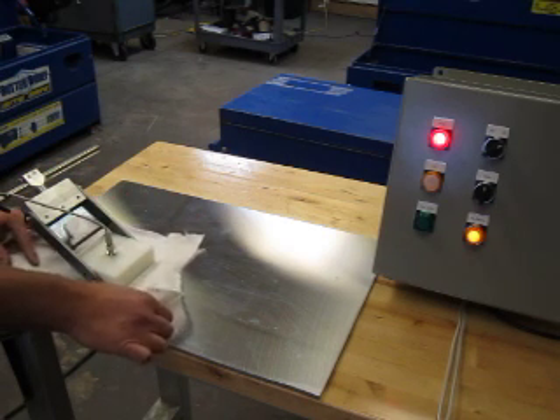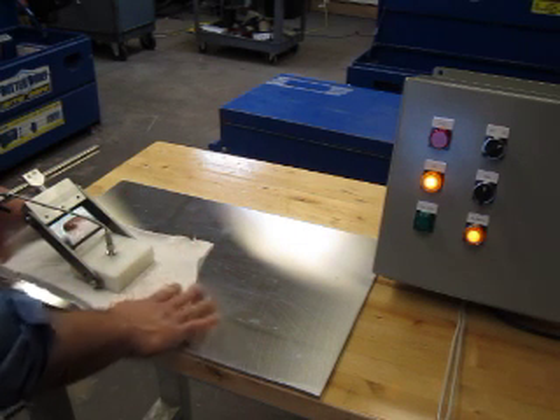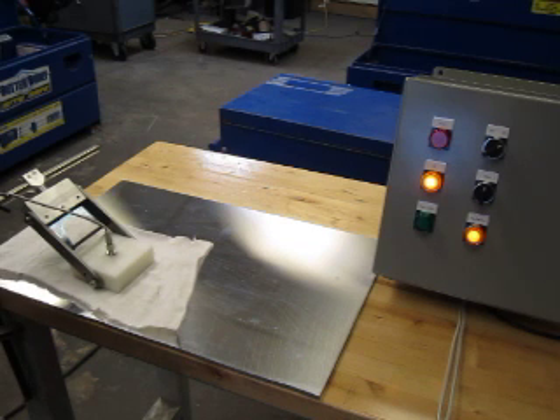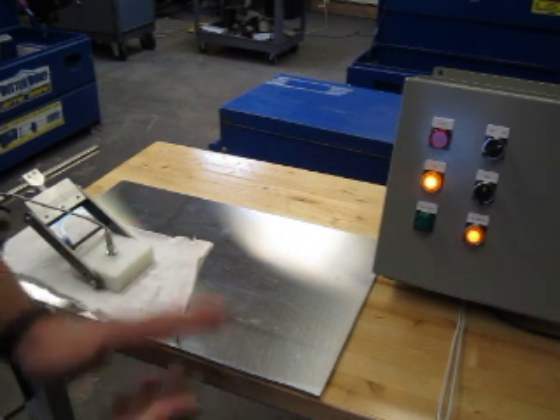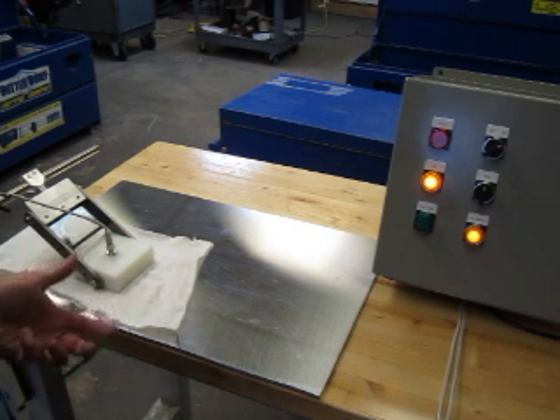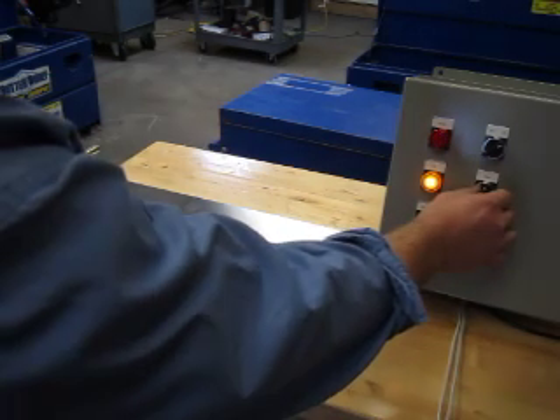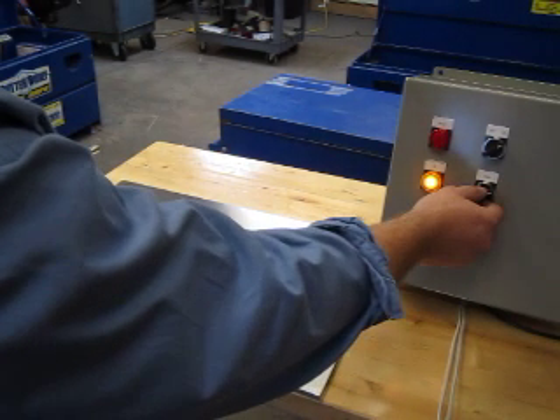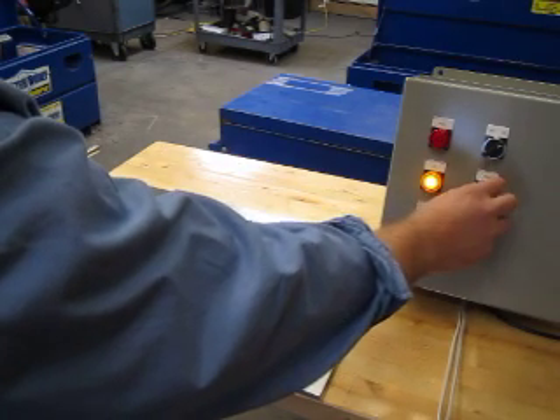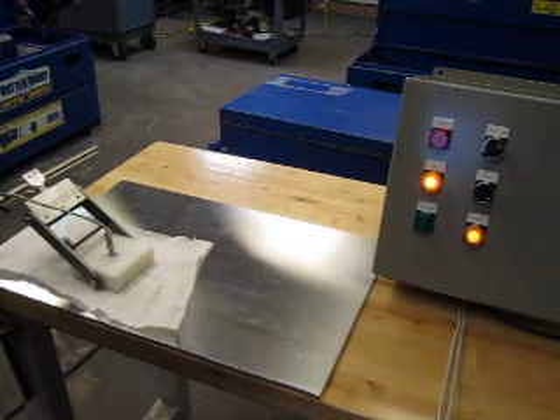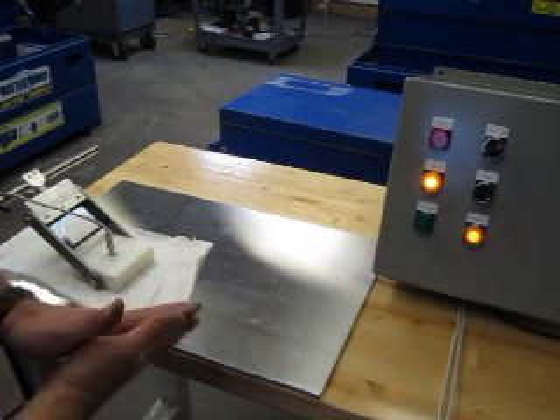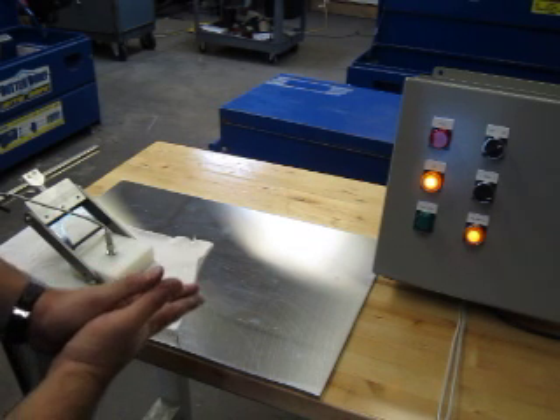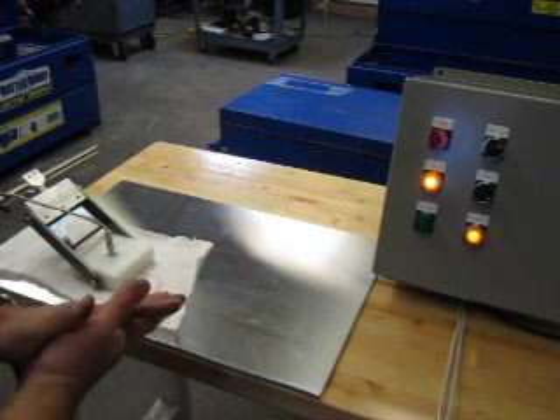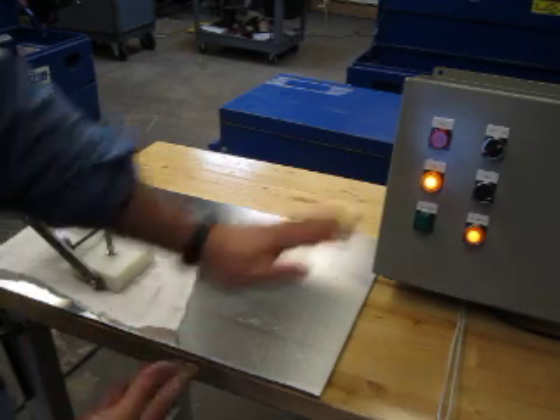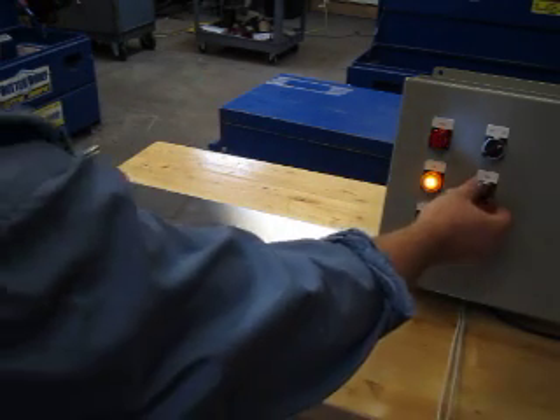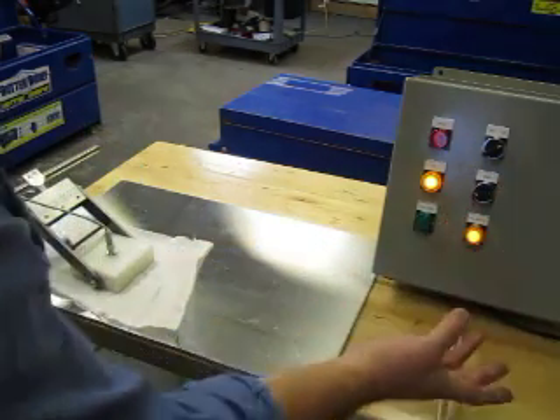you may find that you're either missing seams or the thing keeps shutting your machine down even though there's not a seam there. This dial right here is a sensitivity adjustment. If you turn it this way, the system is less sensitive to changes. So you will need to see a bigger seam pass by in order to trigger the detector. If you bring it this way, it's going to be more sensitive.